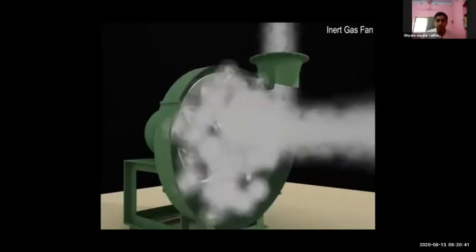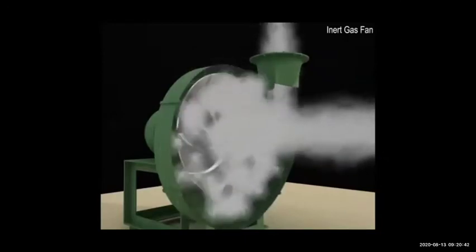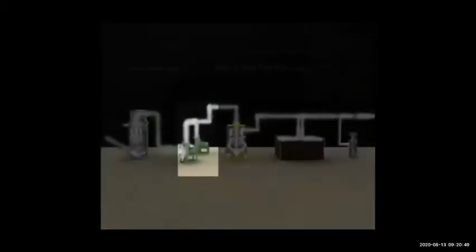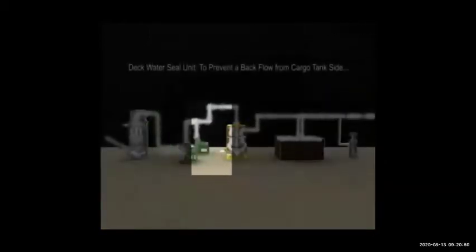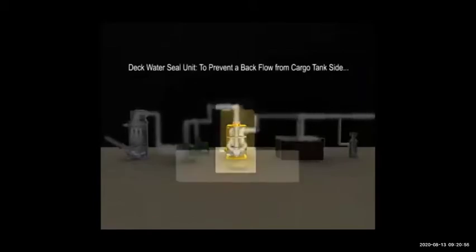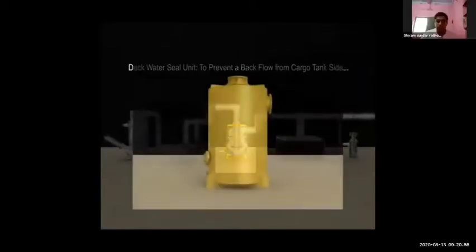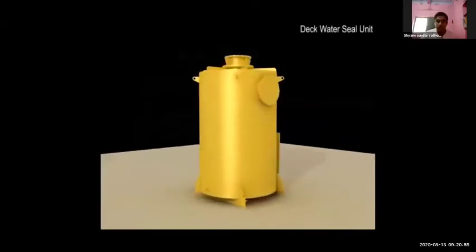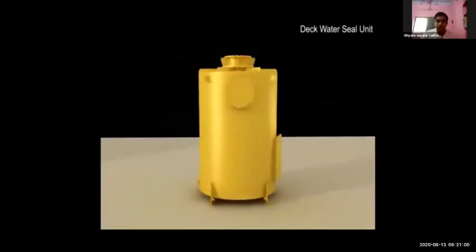The capacity of the blowers is 1.25 times the largest cargo tank. The ship is 203 meters long and tanks sometimes already have some pressure, so we have to put inert gas in the tank with pressure. After the fan, the gas will go to the deck seal. These are all the main parts.